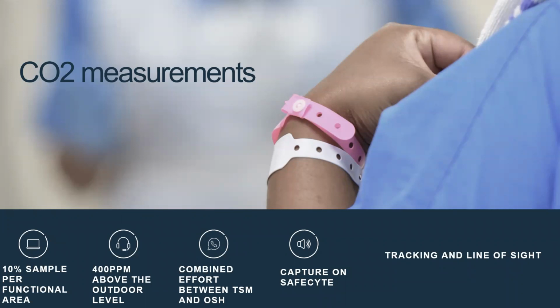Typically you take a measurement from the outdoor condition. Let's say it's 400, because that is what ASHRAE prescribes. Then we go measure inside the room and we get 650 as an example. We know that there's a 250 parts per million carbon dioxide buildup in the air, generated by the people in the room, which is an allowable tolerance, because you have to be 400 above the set average of 400 as prescribed by ASHRAE.